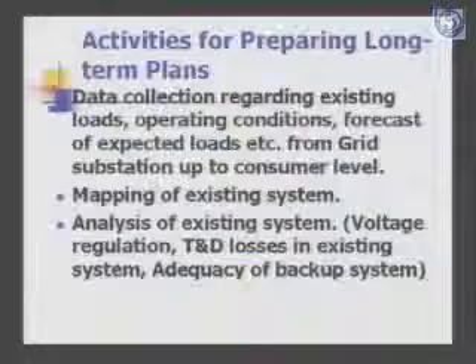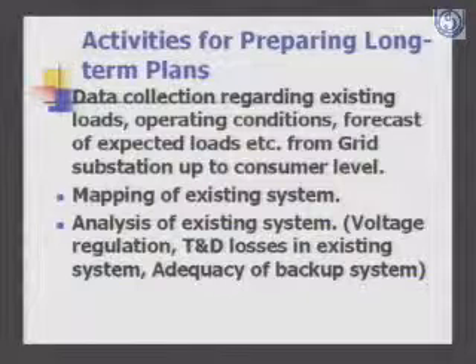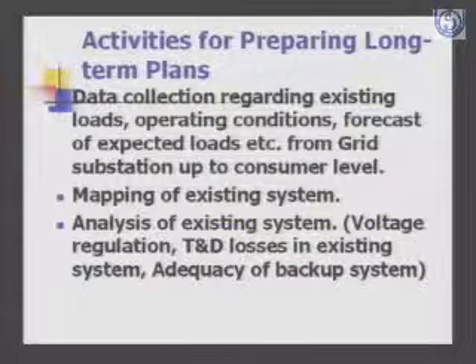If you consider that the span length is 70 meters, no two poles will actually be located at exactly 70 meters, because of the physical constraints in locating the poles or the distribution system. So you need to map the entire system to get the lengths, conductor sizes, the loads, each and every consumer's load, his sanctioned load, his contract demand—everything needs to be mapped first if you want to plan, because unless you know the existing system, you cannot plan improvements and additions to meet load growth and improve the system.